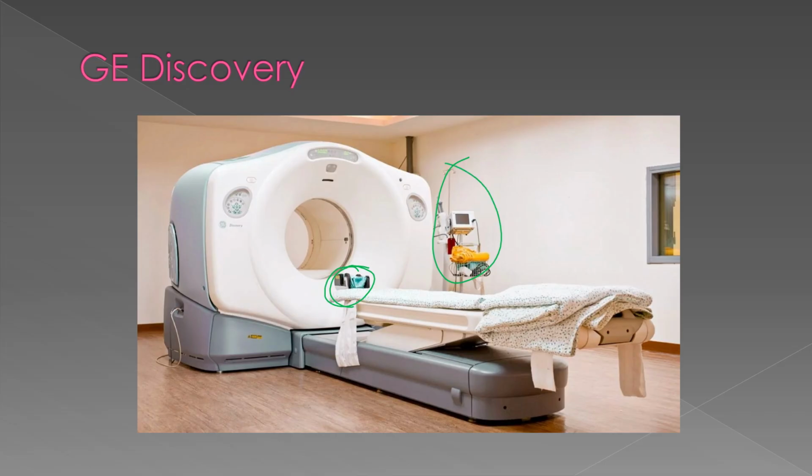Over here, you have a contrast injector. So this one is used for both. That's not like a Siemens GE thing. If the CT has enough slices and a capability, it can be used for diagnostic CTs. Same thing on this one though, you have a control pad, you have your lasers on the top and the sides, you have a little information screen up here that tells you the height and the, I forget the word for that, but how far in the bed position is.